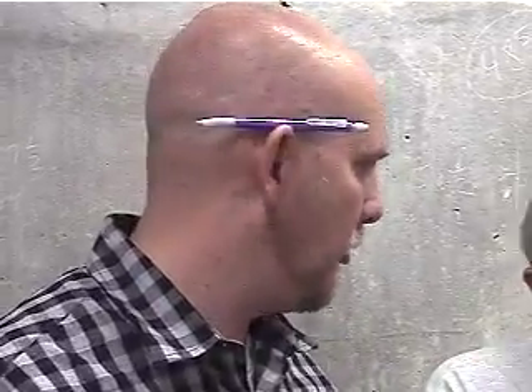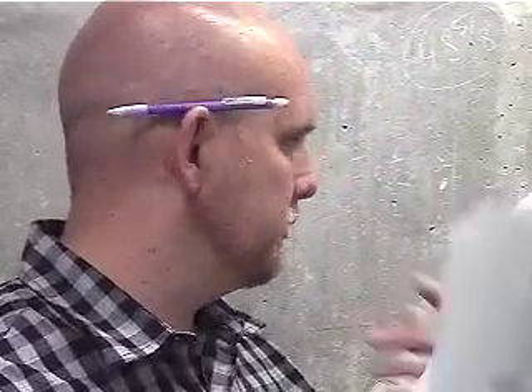Now, we did come out when we did the startup. We came and we aligned all of these, so they are good to go now. Down the road, you can give us a call anytime. We'll come out and help you guys, no problem. We're just local, kind of by the airport. We're more than happy to work with you guys on these pumps. So again, that's the key. If you do see shavings, don't just replace the coupler and move on. Resolve the issue. That means the alignment has probably gotten out somehow, and it's a simple fix to correct the alignment.